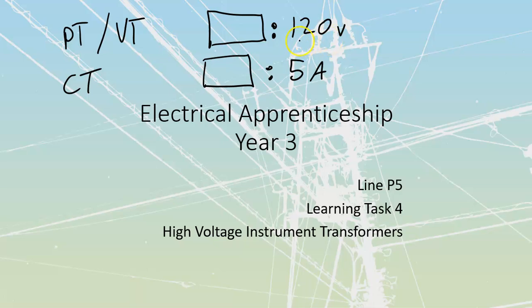And what we get here on the secondaries is always going to be based upon full rated current flowing in the primary. In other words, if we had a 400 to 5, we would only get 5 amps when we get 400. If we only had 200 amps, we would get half of that, 2.5. But if we got 600 amps, we would get 7.5 amps flowing out of this.